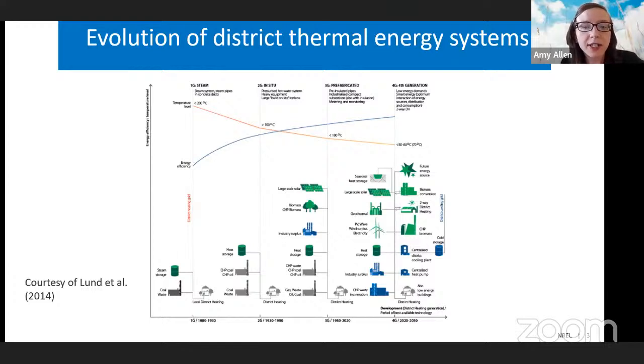Lund and others have often characterized the evolution of these systems into either 4 or 5 generations. I'll use the nomenclature from a paper by Buffa in 2019, which characterizes these systems into 5 generations, with emerging 5th generation systems operating at network temperatures between 15 to 25 degrees Celsius and leveraging water source heat pumps at connected buildings to further temper the water to meet the building's heating and cooling loads.